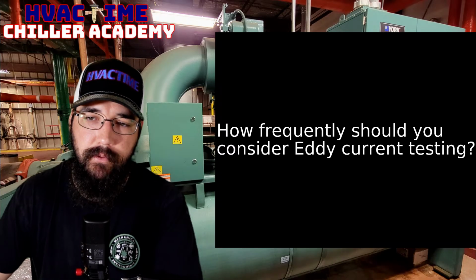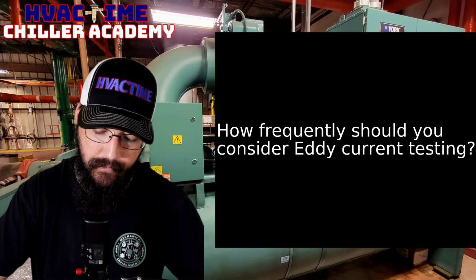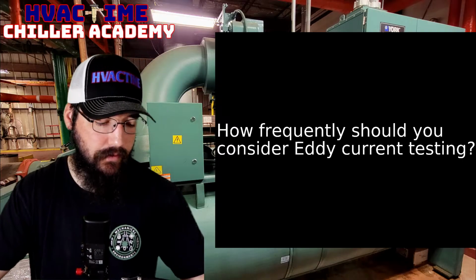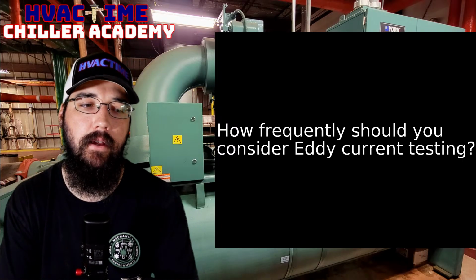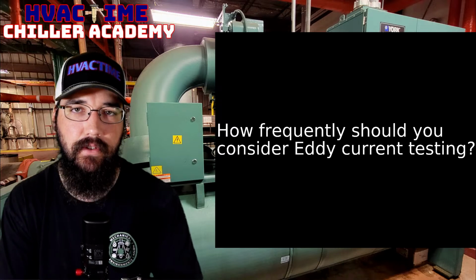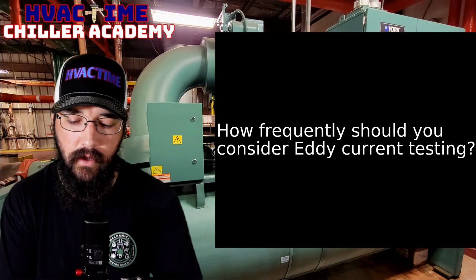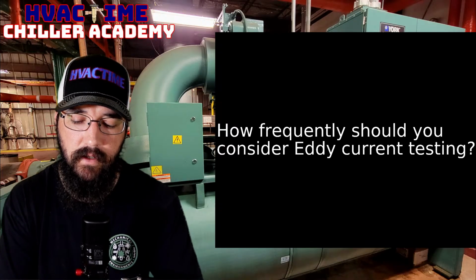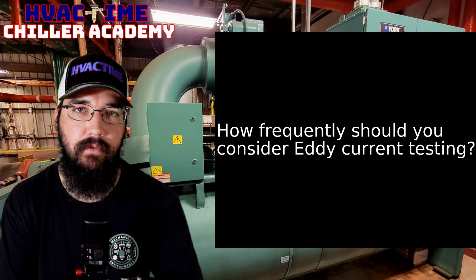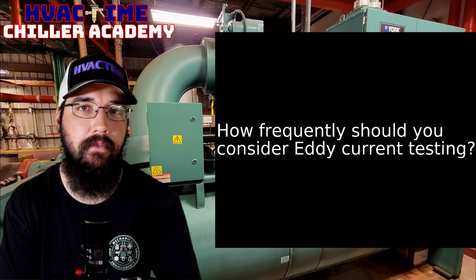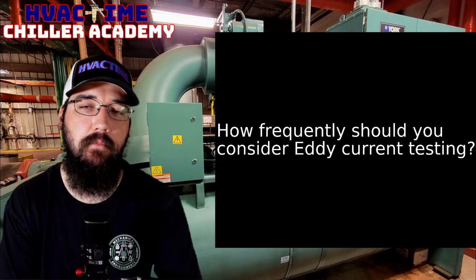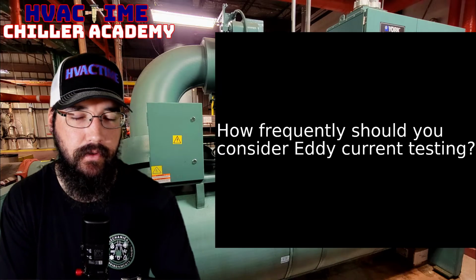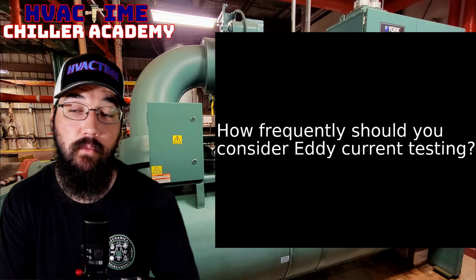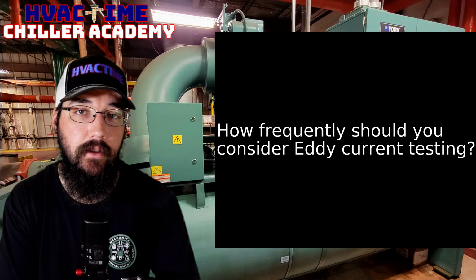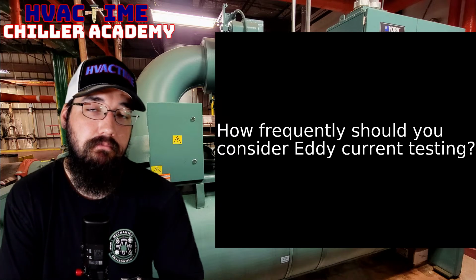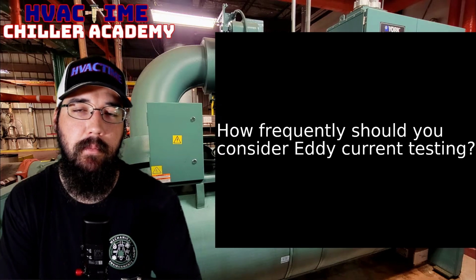So, how frequently should you consider eddy current testing? My default is 5 years. So I just stick to a 5-year schedule unless there's reason to do it otherwise. There are some reasons. If we have a specific condition in the plant, there are some plants that have a more critical schedule. They stick to a more rigorous schedule, so we have to adhere to that, and they may want it done annually. There are some facilities that literally want an eddy current every single year. It's just their preference. A lot of times they may have very specific reasons as to why.